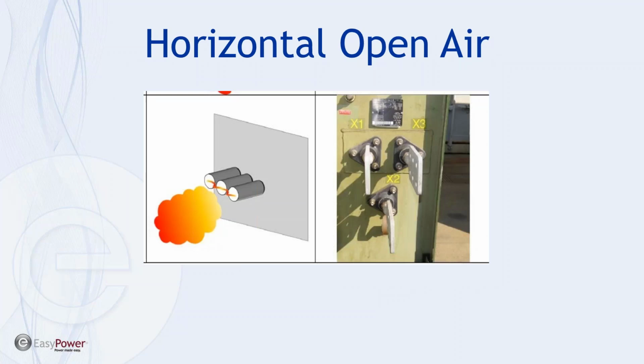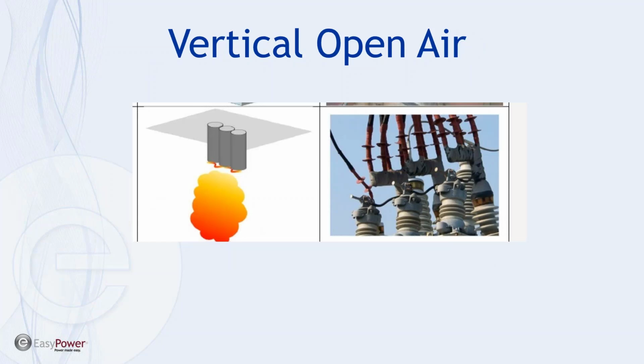Horizontal in open air, essentially, and this is terminals on a transformer, the radiation pattern is directly out from the stub end of the buswork or the termination, and consequently this puts the operator at more increased risk for heat radiation. When we look at vertical orientation, again, the operator is standing out in front of this and the radiation pattern is blooming down. This is not dependent upon gravity. This is dependent upon the relative placement of the operator. So if the technician is directly under a termination that looks like this, it would more correctly be defined as horizontal because of the radiation pattern and exposure to the operator.